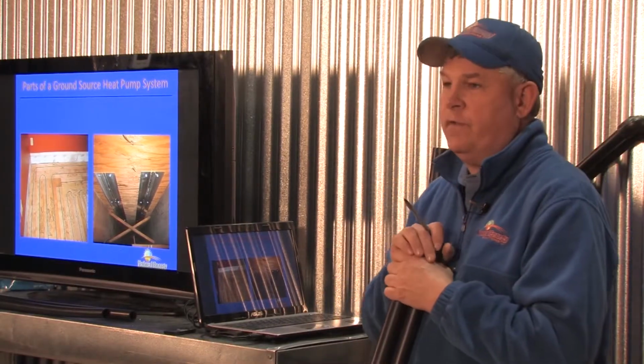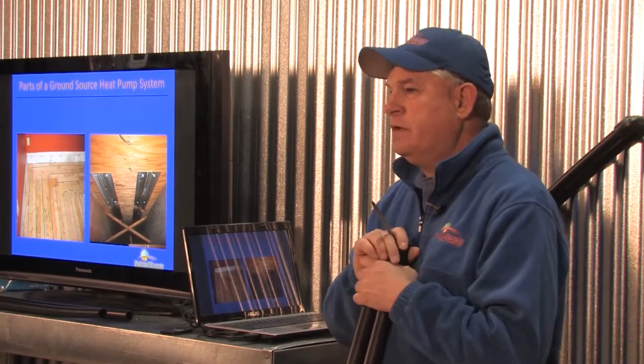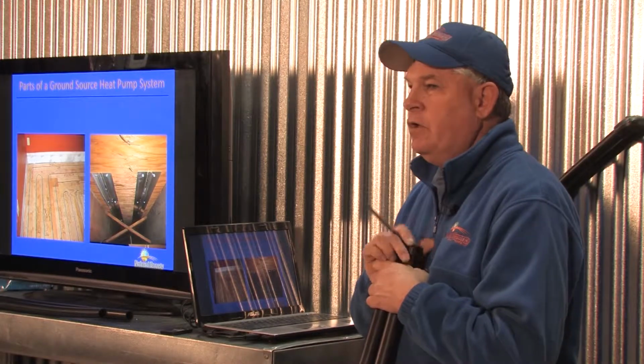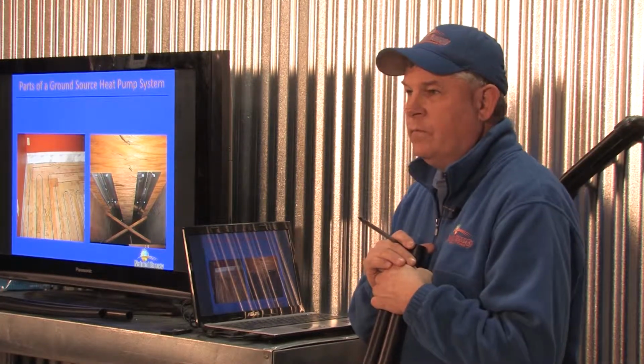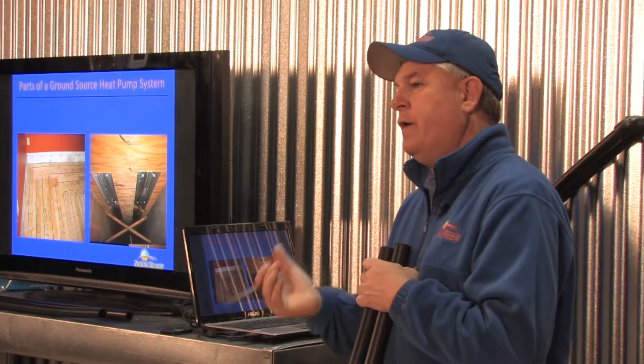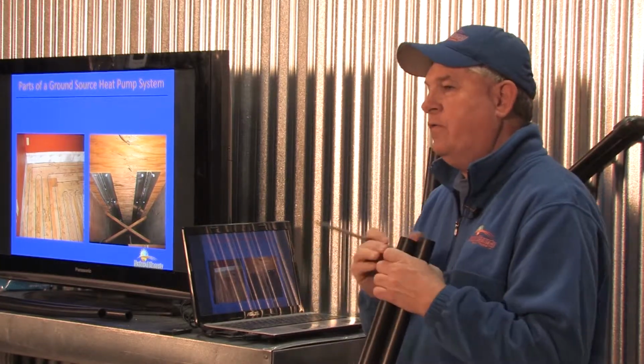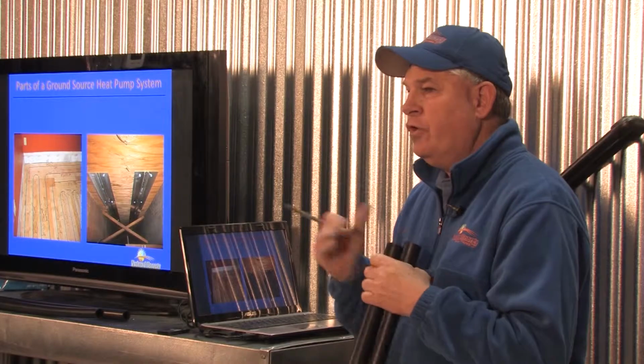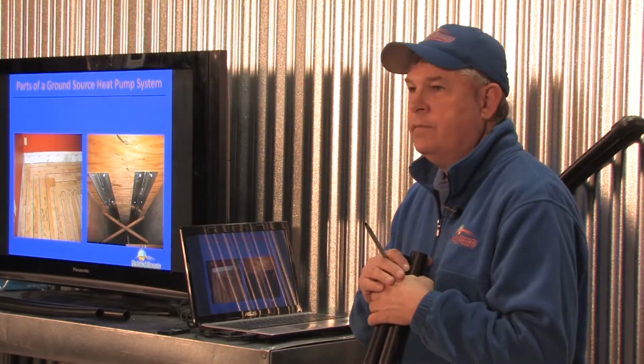Hydronic systems are wonderful, but the majority of people still would like air conditioning. The units are fully reversible. So if you don't install ductwork or don't have a forced air system, I can't give you AC. Your unit's just taking the summer off. And half the year you're not getting return on your investment. So by far the majority of the times we're either installing or modifying or reusing someone's forced air ductwork system. Okay? But generally they're the only two ways we have to move energy, air or water.